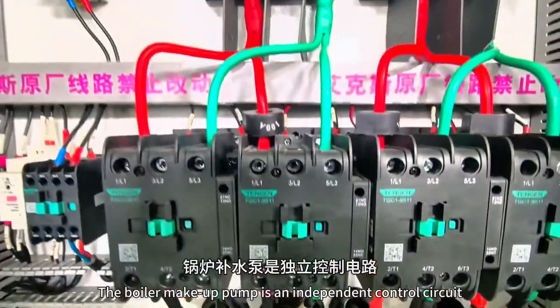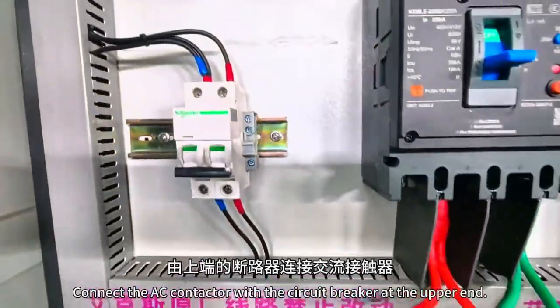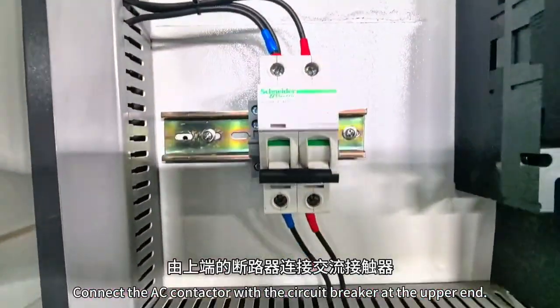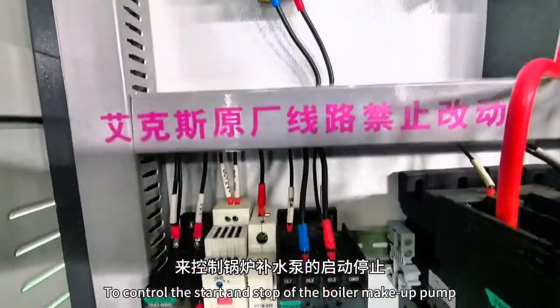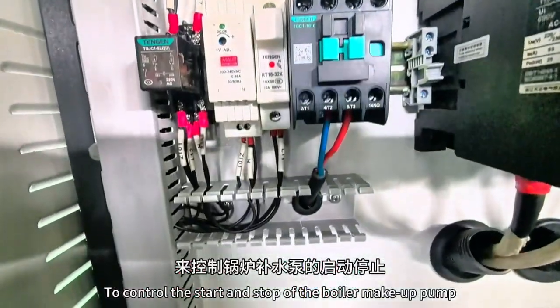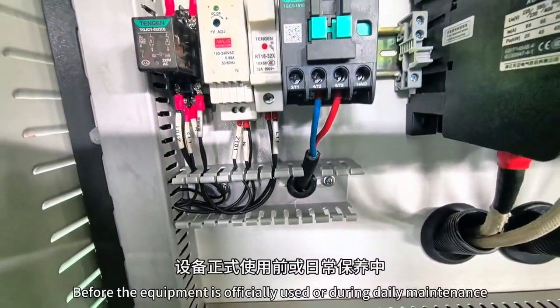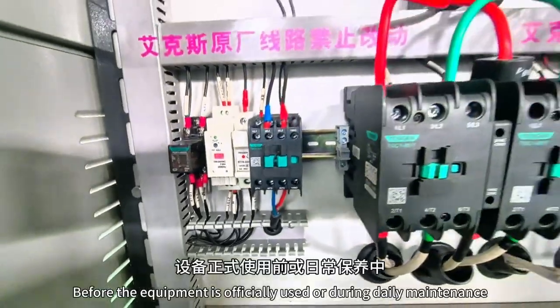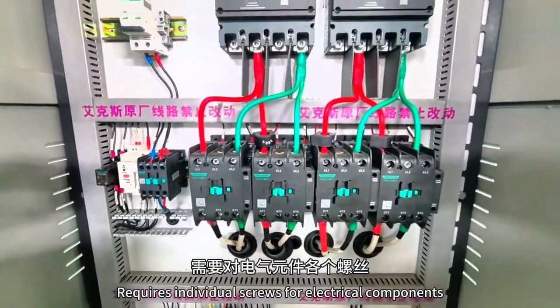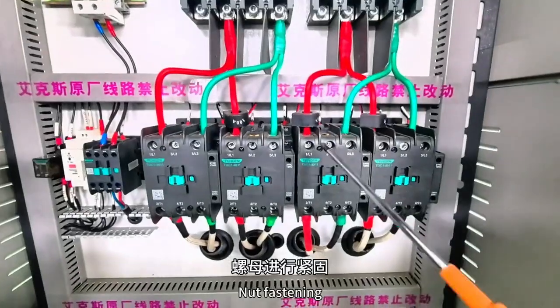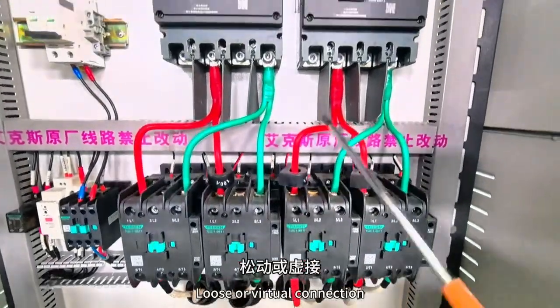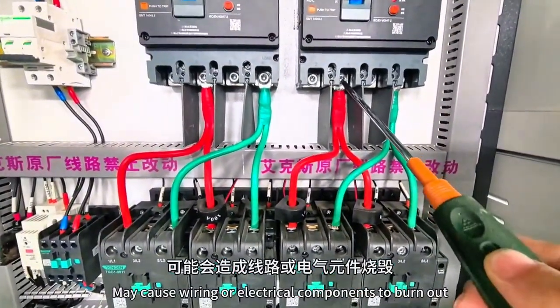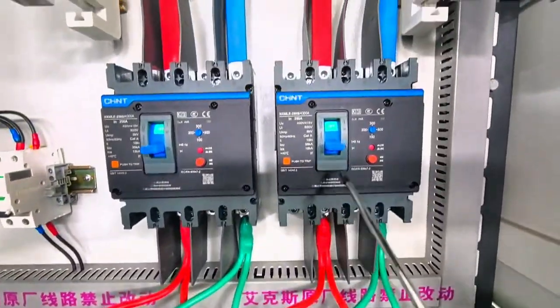The boiler feed water pump is an independent control circuit, which is connected to an AC contactor by the upper circuit breaker to control the start and stop of the boiler feed water pump. Before formal use or during daily maintenance of the equipment, it is necessary to tighten the screws and nuts of the electrical components. Loose connections may cause damage to the circuit or electrical components.